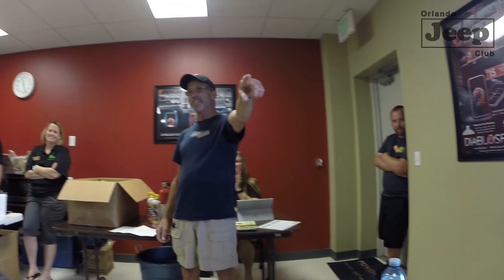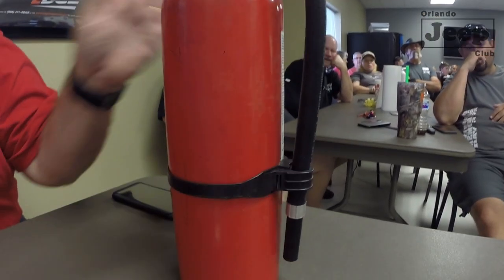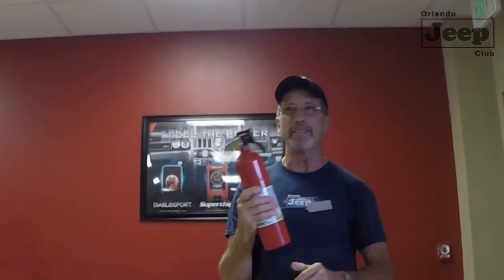You can also use a rubber mallet — when I did inspections I would pound it on the side back and forth until it was free-flowing. On the side of the fire extinguisher there's a rubber hose — remove that hose and make sure it's unobstructed. Many have a quick safety pin; the one Ellen has here has a breakaway zip-tie type. Make sure your safety pin is locked into the valve handle to prevent accidental discharge.